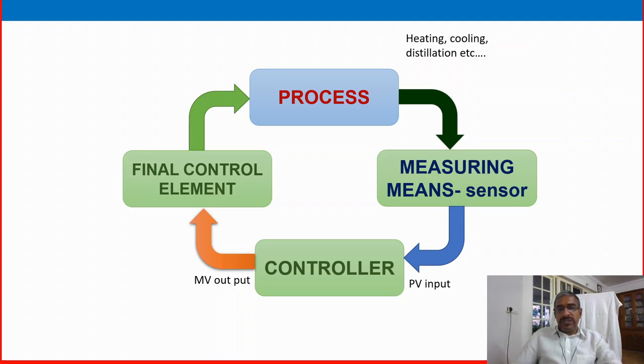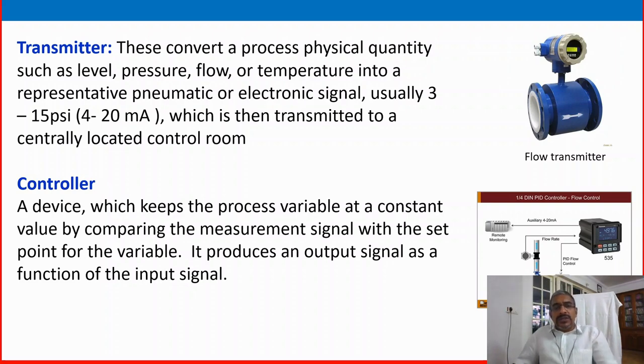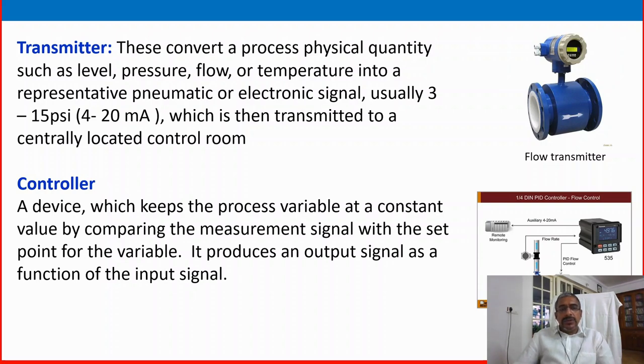This is the simple variable process control loop. Please note: process variable (PV) is the input and manipulated variable (MV) is the output. The transmitter converts a process physical quantity such as level, pressure, temperature, or flow into a representative pneumatic or electrical signal — usually 3 to 15 PSI or 4 to 20 milliamps — which is then transmitted to a centrally located control room.